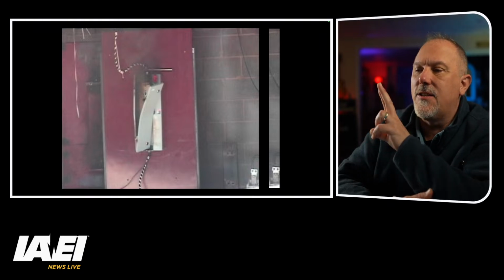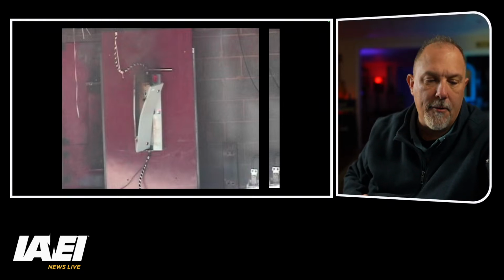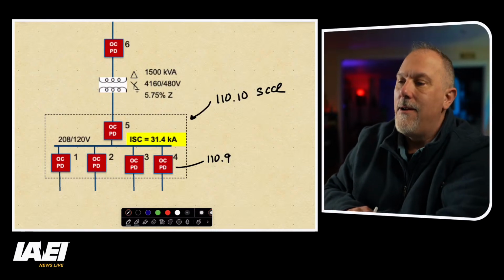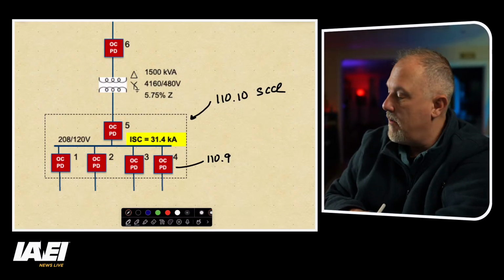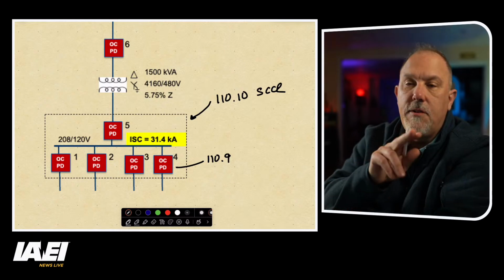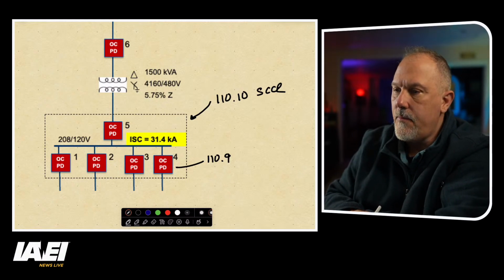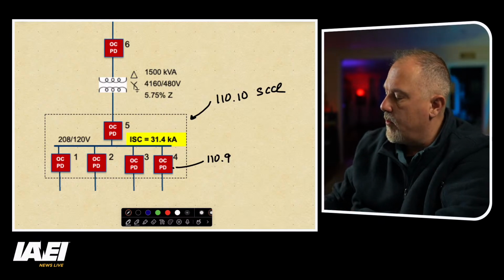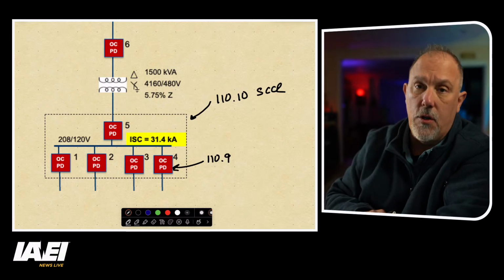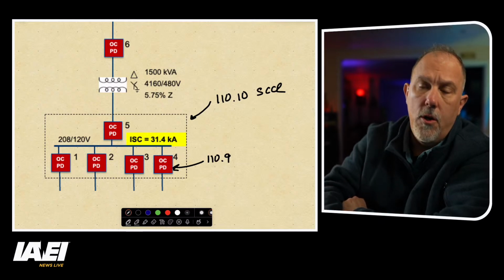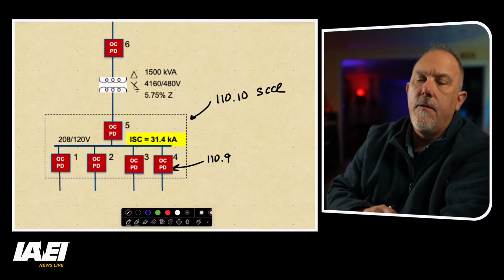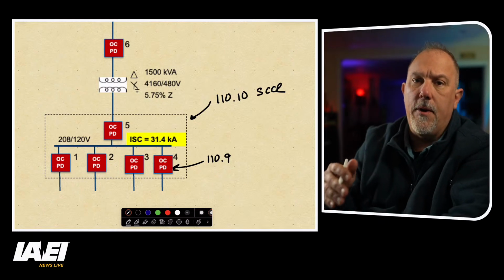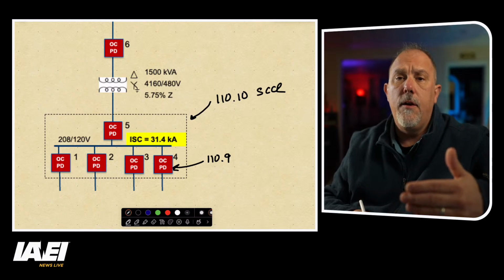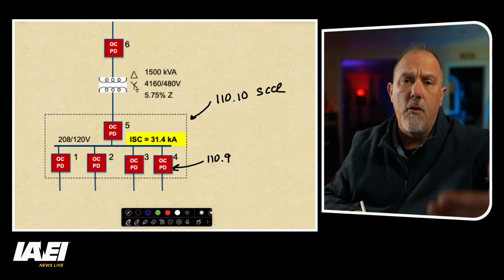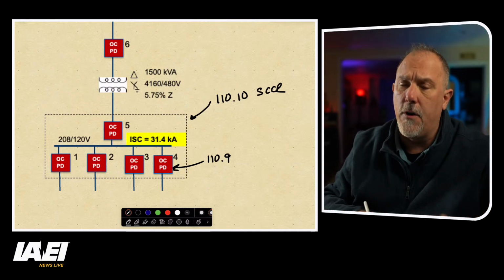So there are two key sections, and Laurel hit it right. Our research department said it right. Laurel from Omaha identified two key sections. 110.9 is interrupting ratings. So whenever we look at overcurrent protective devices, whether it is a fuse or a circuit breaker, we want to make sure that the interrupting rating is adequate, meaning the interrupting rating of the overcurrent protective device is greater than the available fault current.